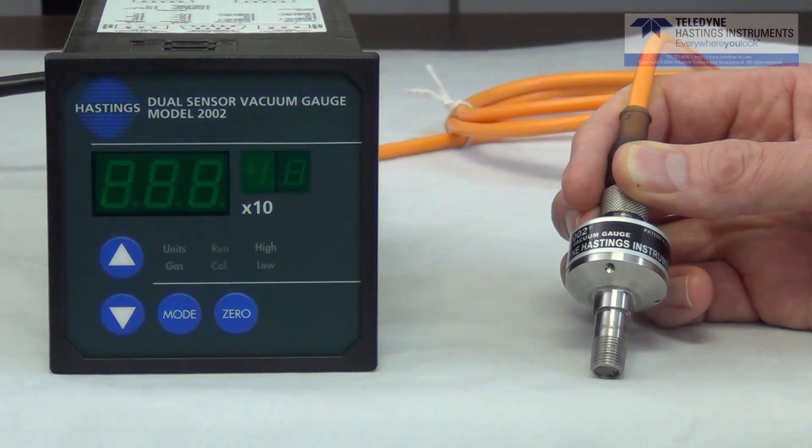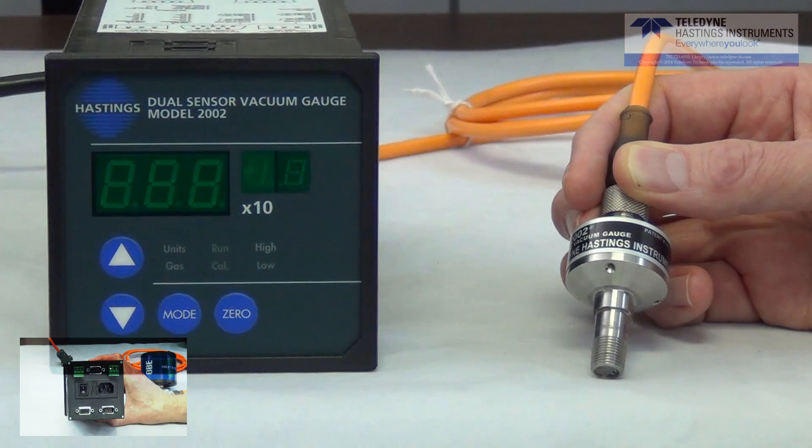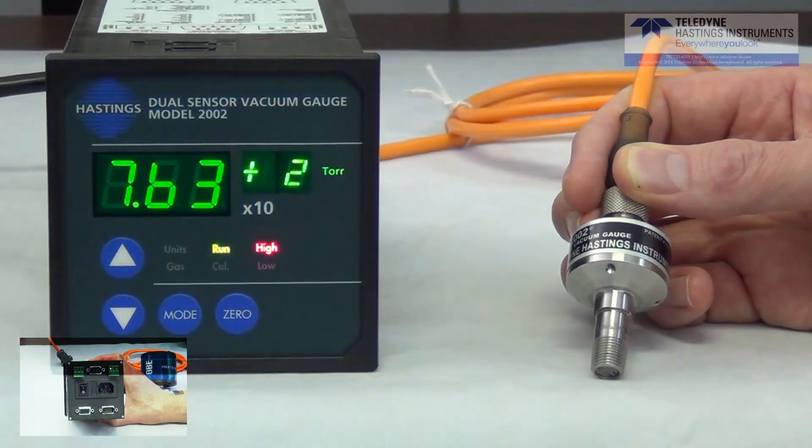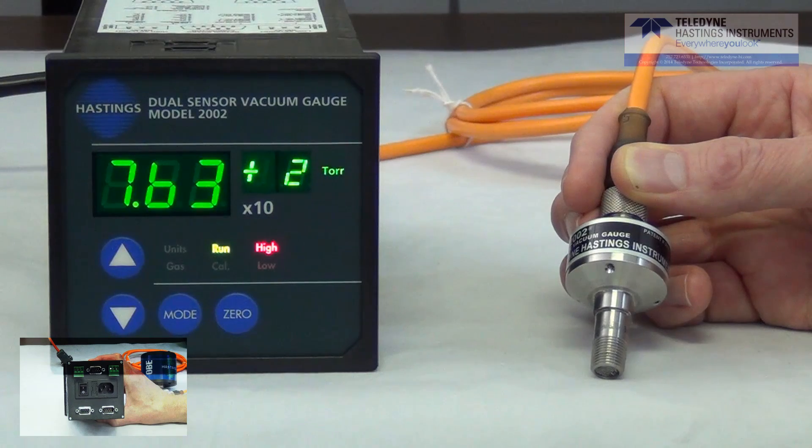So now let's look at the operation of the 2002. When the instrument is initially powered, the microprocessor in the readout goes out and gathers the gauge tube's calibration data. Remember, it's stored on the memory chip that's in the cap assembly. So you always want to make sure that your cable is connected before you turn on the power.